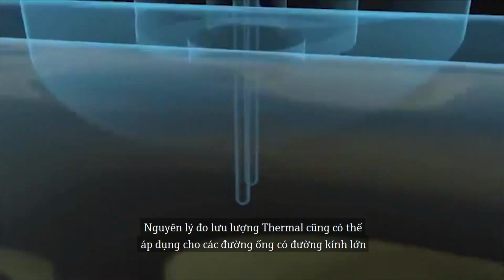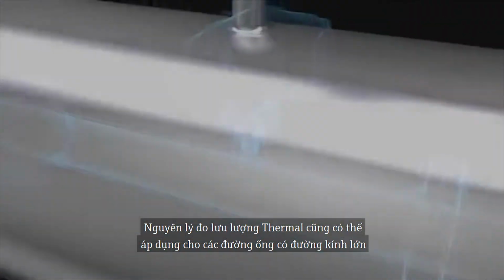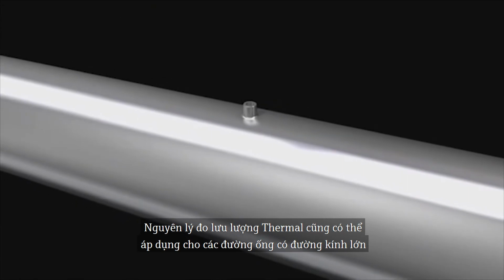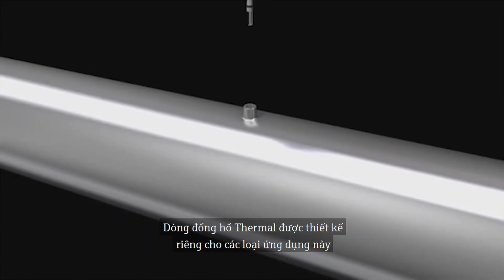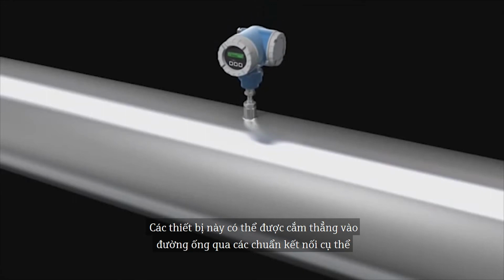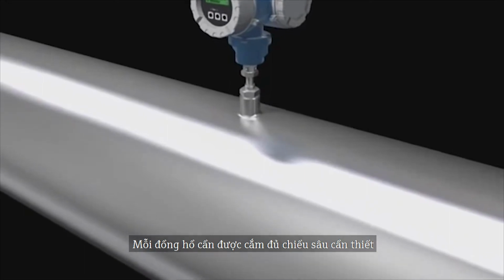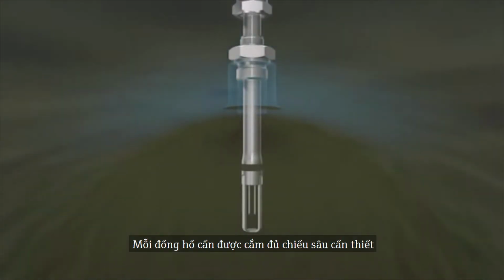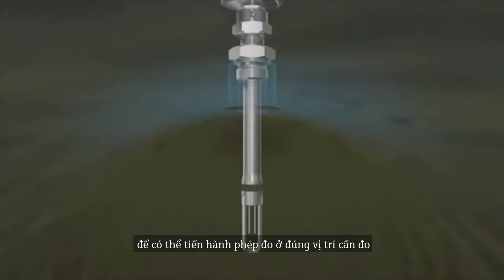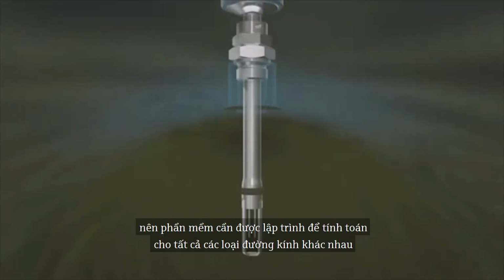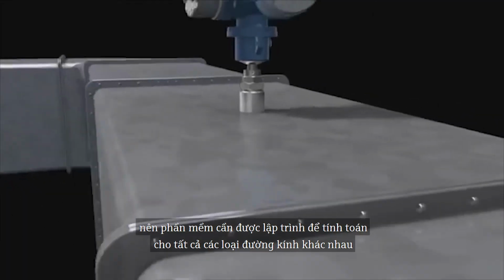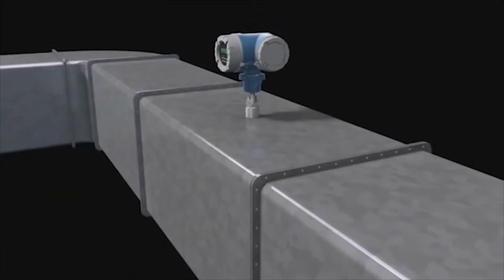Flow measurement using the thermal principle is also possible in large pipes and ducts. There are meter types designed specially for this application. They can be inserted directly into the pipe via a standard process connection. It is important that the required insertion depth be respected so that the measurement is carried out at the correct point. For that reason, it's essential to program the actual internal pipe diameter for all insertion meters.